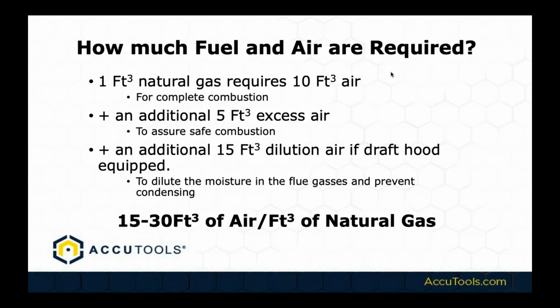So it is completely normal for a combustion process to produce 0 parts per million CO, completely normal. And you'll see that all the time if you have a quality analyzer that has a NOx filter in there, like the BluFlame does. Now, the excess air we want to carefully control, so we don't want any more air than we need, because all that air does is go in and go out, and it doesn't provide any function except for safety, but it robs the flue gases of their heat energy and it robs the appliance of its efficiency.